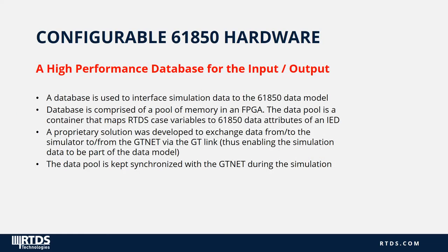A high-performance database for input and output. A database is used to interface simulation data to the 61850 data model. The database is comprised of a pool of memory inside an FPGA. The data pool is the container that maps the RTDS draft case variables to the 61850 data attributes for the IED. A solution was developed to exchange data from and to the simulator to and from the GTNet via a fiber-optic link, thus enabling the simulation data to be part of the data model. This data pool is kept synchronized with the GTNet during the simulation.